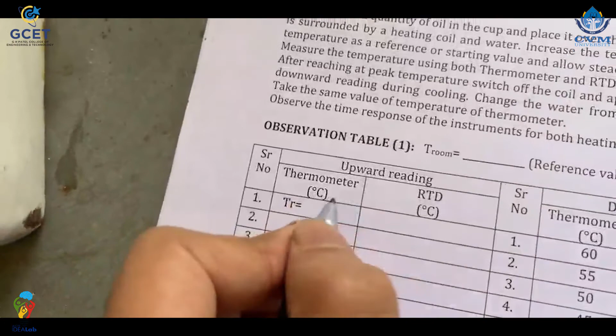At this time, the glass tube thermometer is showing a value of 31 degrees Celsius, and at the same time the RTD is showing 31.2 degrees Celsius. So we get a difference of 0.2 degrees Celsius. We have to note this down in our table as the reference temperature.